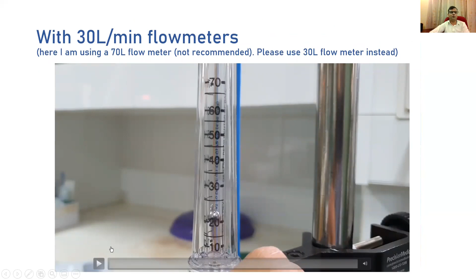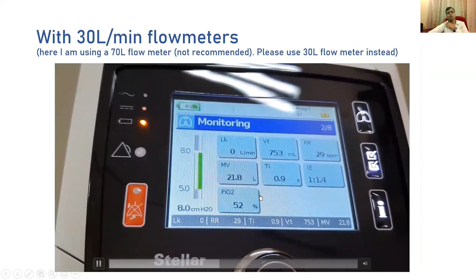First of all, we'll see what happens with 30 liters. Generally, as I told you, because it entrains room air, it cannot deliver a high concentration of oxygen. Here I'm getting about 55% oxygen. Now if I increase the flow to maybe 40, I might get slightly more. I'm just trying to simulate the flooding in a 30-liter one. So I'm getting more oxygen, it goes up to about 60, 65. The tidal volume is now about 700.